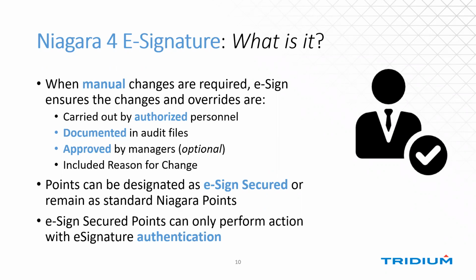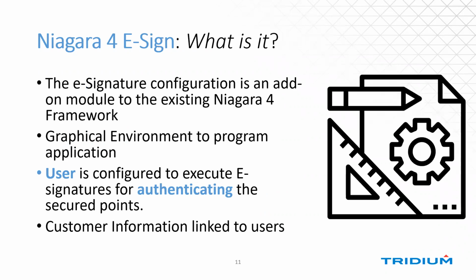So if there's areas in the same system that don't need to be as secure, like just changing a thermostat in a lobby or something, you don't want to have 2 people sign off every single time. These can exist in the same system, but we just restrict such things through category services, role services, user service. Make sure whoever has access to the specific points that need to be validated are performed with authentication, and that will make sense in the application.